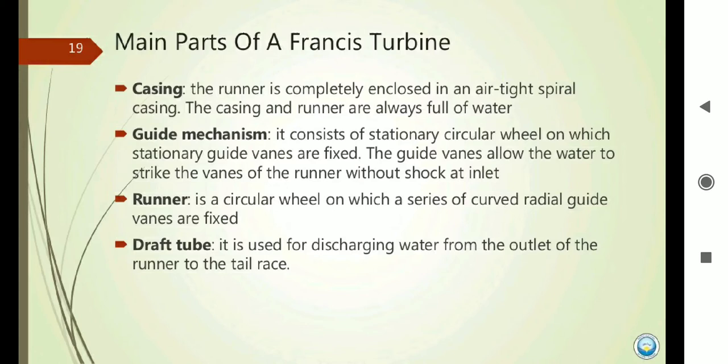The guide mechanism consists of a stationary circular wheel on which stationary guide vanes are fixed. The guide vanes allow the water to strike the vanes of the runner without shock at the inlet. The runner is a circular disc on which a series of radial curved vanes are fixed. The draft tube is used for discharging water from the outlet of the runner to the tailrace. Draft tube is used to decrease pressure; without it, bubbles form — that is called the cavitation effect — which can damage the turbine.